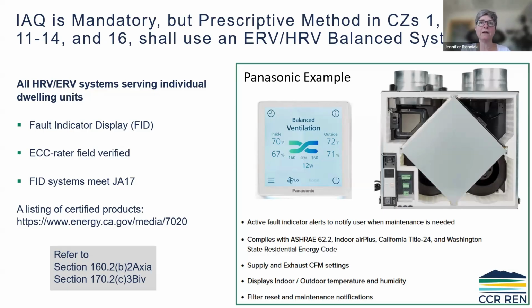fresh outside air into the space, if it's winter, it's going to be doing a really cold air dump if you didn't have the heat exchange. Or if it's really hot outside, it's going to be dumping just warm air into the house that you're trying to air condition. And at the same time, you're pushing your air conditioned air out. So that's why the heat exchange. And that's kind of why it's a prescriptive part of those prescriptive components for those climate zones.